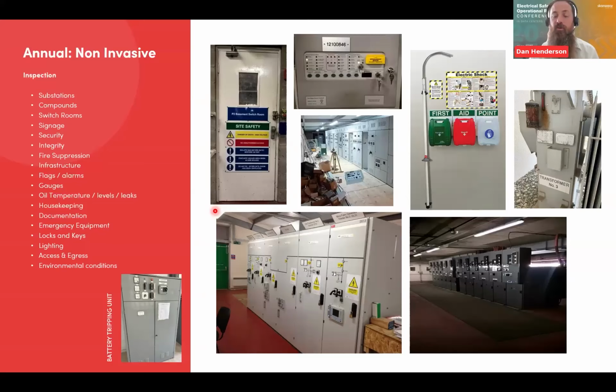So again, it's good to make sure you've got those periodic inspections planned in. That's why it's important, and you'll notice these subtle differences, which might be just linked to environmental conditions. So yeah, any leaks, you might have leaks from compound fill boxes, oil circuit breakers, things like that. Housekeeping is really important. So there's a couple of pictures there of storage of combustibles, which, from a loss prevention risk management perspective, you don't want anything in there where you can have a fire danger.